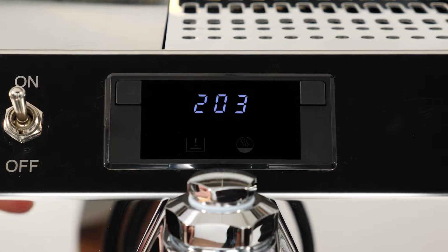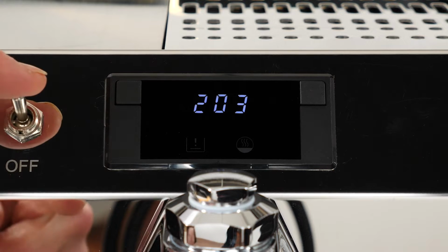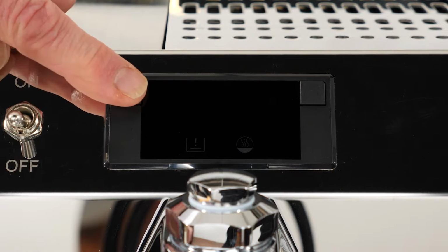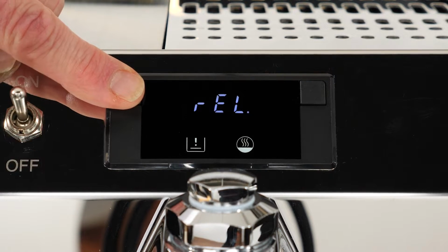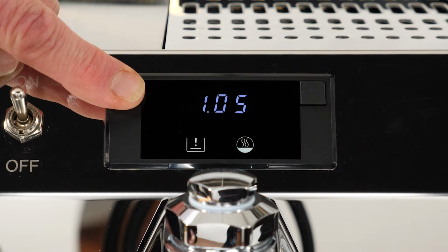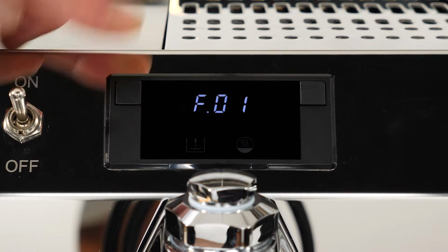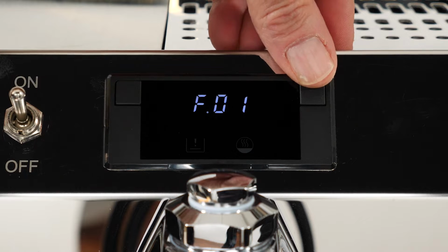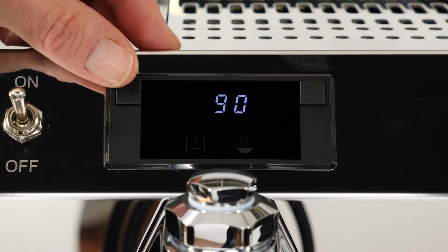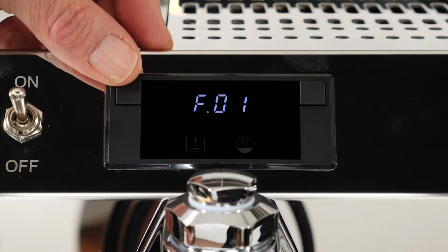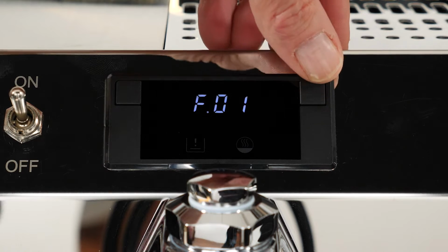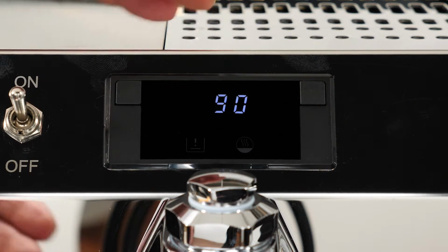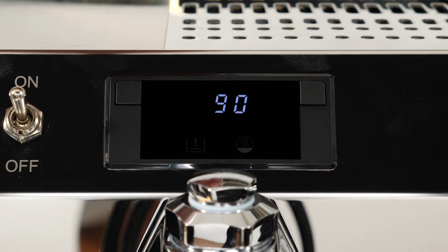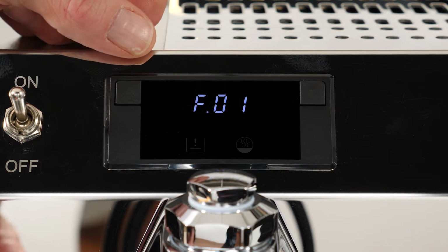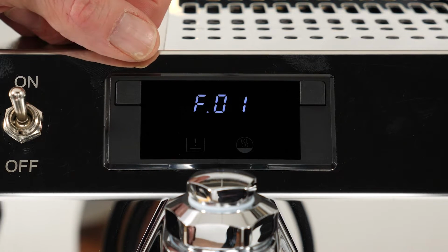Let's show you how to get into the technician menu. Turn the machine off, press down on the left button, turn the machine on while continuing to hold that left button until you see F.01. That's the steam boiler filling timeout, set to 90 seconds, so we'll leave it there. That boiler filling timeout means the machine will attempt to fill the boiler for 90 seconds—if it doesn't accomplish that, you'll get an error code and need to figure out why it's not filling.